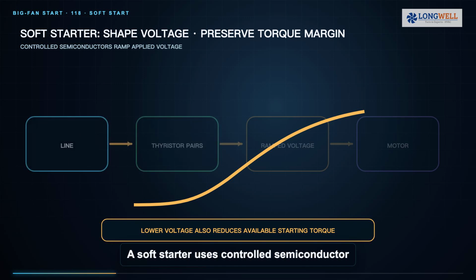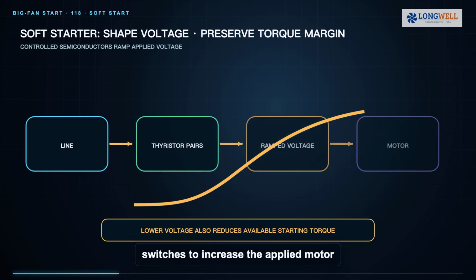A soft starter uses controlled semiconductor switches to increase the applied motor voltage during the start. Reducing voltage can reduce the current step and mechanical shock, but induction motor starting torque falls rapidly as voltage is reduced. If the current limit or ramp is set too gently, a high inertia fan may accelerate too slowly, heat the motor, or fail to reach full speed.